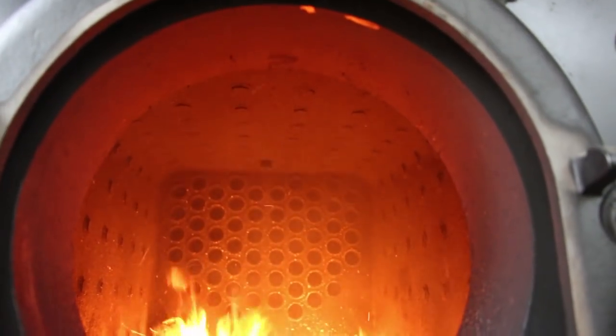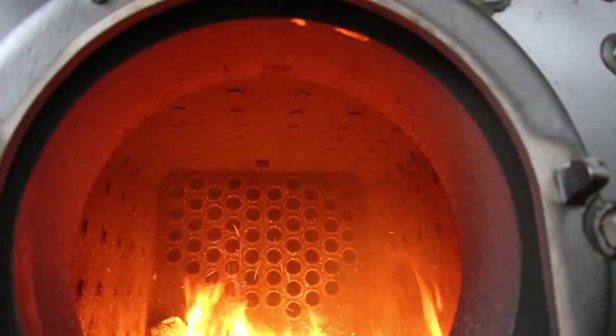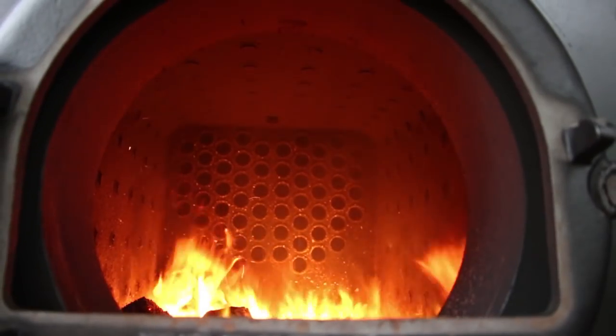If the water actually drops off the top of the crown sheet, it'll melt that metal out and basically cause all the water and steam in the boiler to go down into the fire and extinguish the fire. That's just a safety feature on a boiler like this.